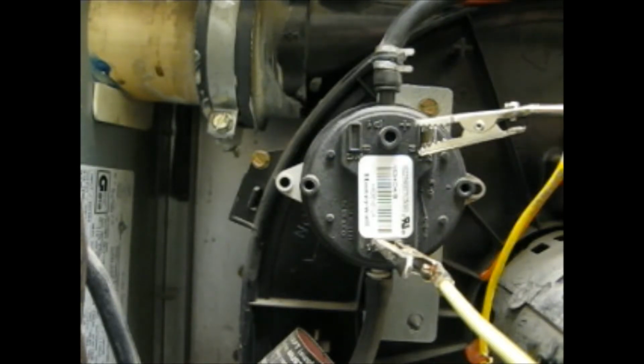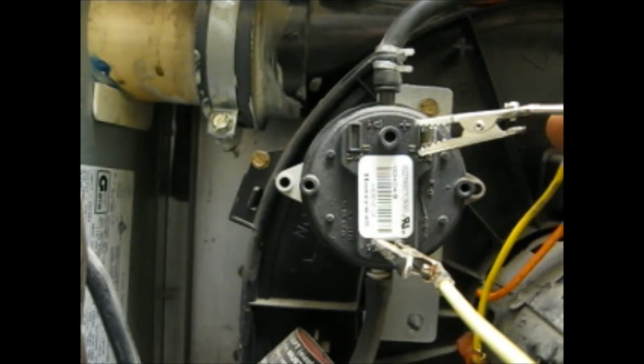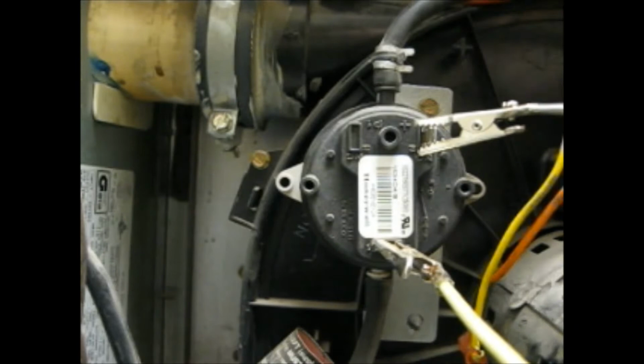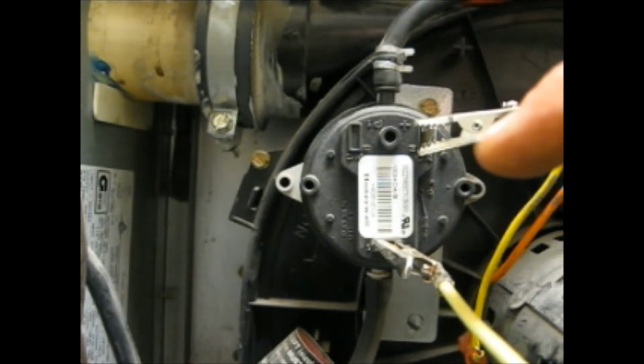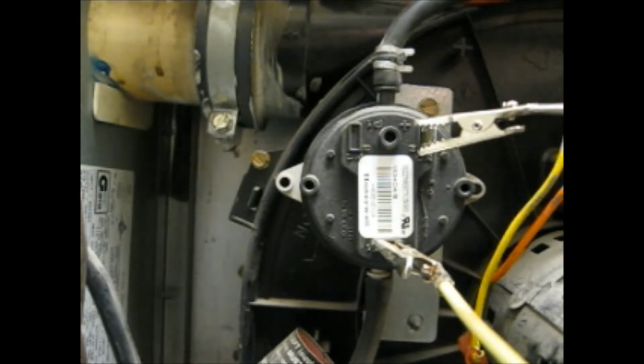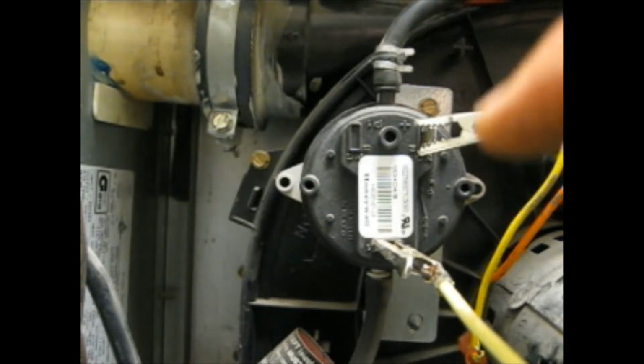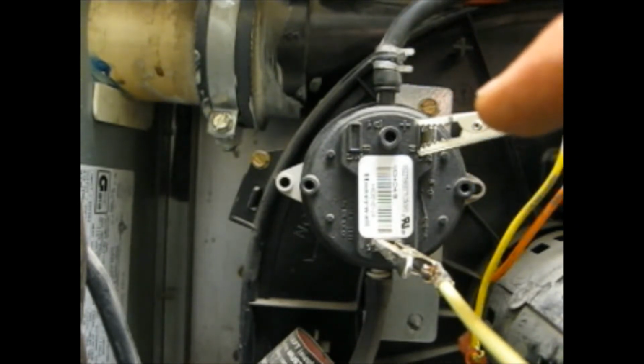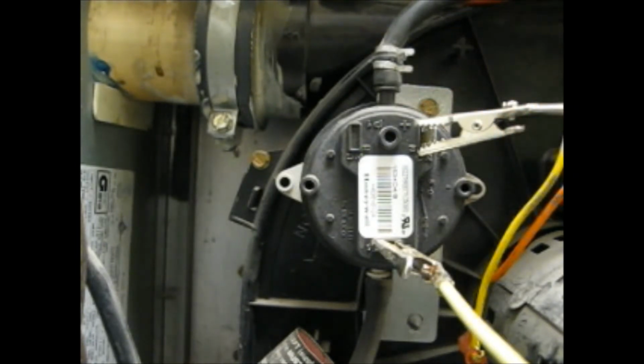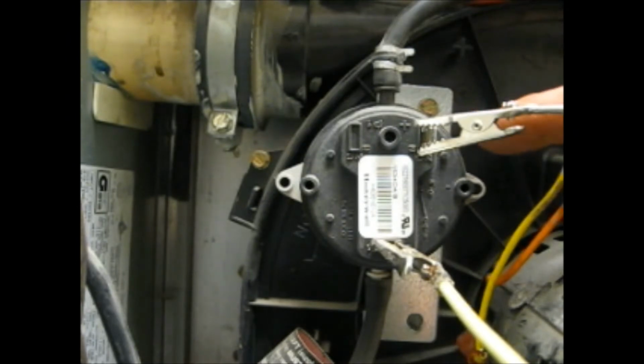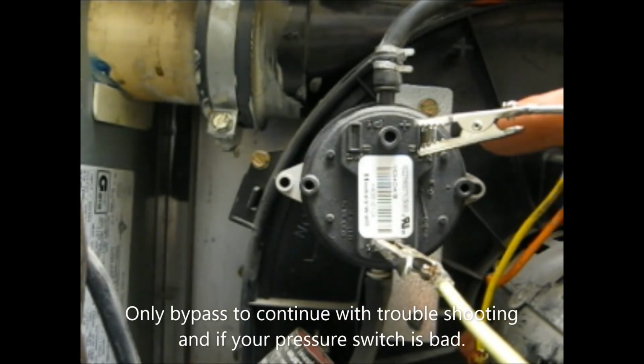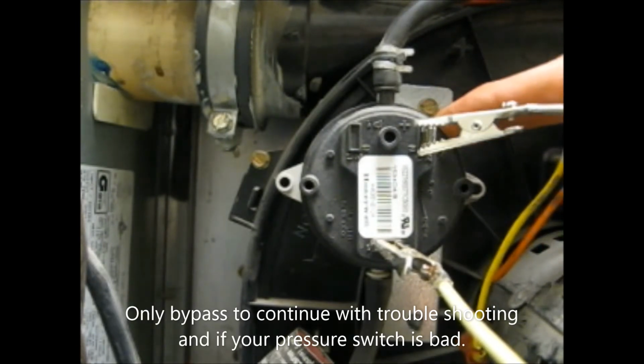But let me warn you about using jumper wires as a bypass. They should only be used for testing only. You do not want to put your furnace into normal operation with a safety device being bypassed. You're asking for trouble if you do so. Once your air pressure switch is bypassed, try your furnace again and see if it starts up. If it does, that's a sure sign that your pressure switch is bad.